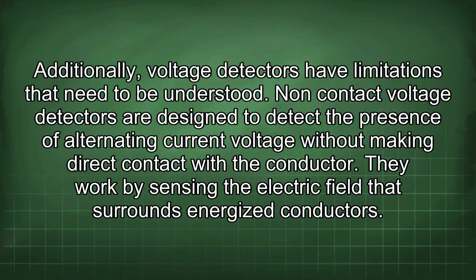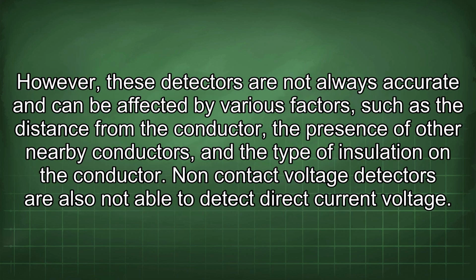Additionally, voltage detectors have limitations that need to be understood. Non-contact voltage detectors are designed to detect the presence of alternating current voltage without making direct contact with the conductor. They work by sensing the electric field that surrounds energized conductors. However, these detectors are not always accurate and can be affected by various factors such as the distance from the conductor, the presence of other nearby conductors, and the type of insulation on the conductor. Non-contact voltage detectors are also not able to detect direct current voltage.